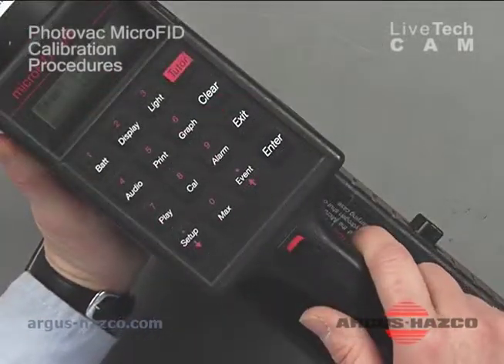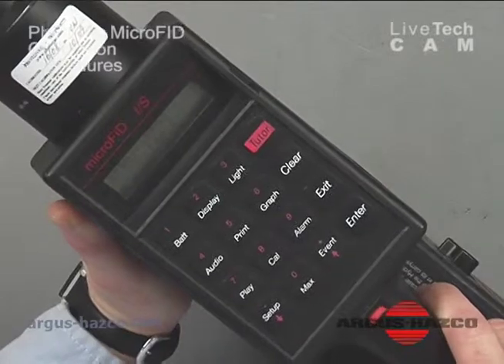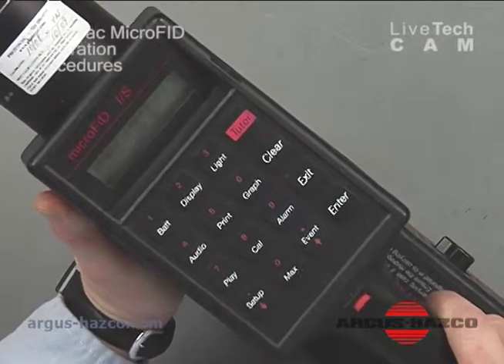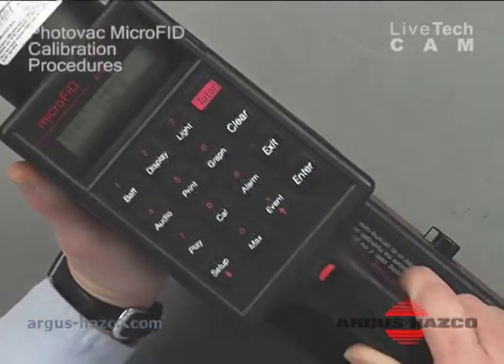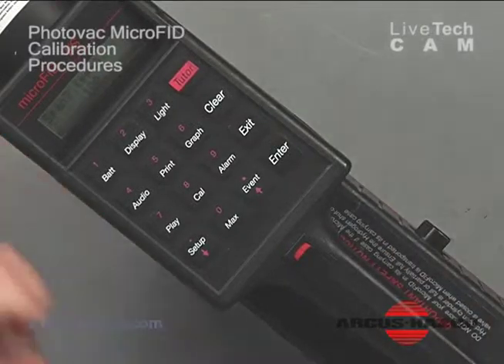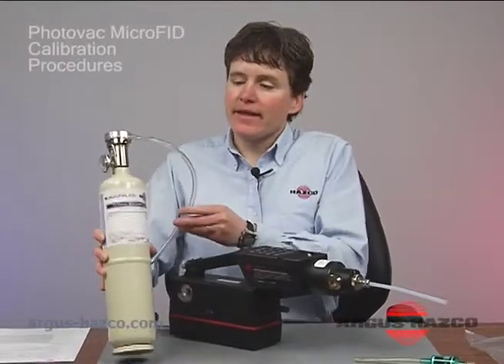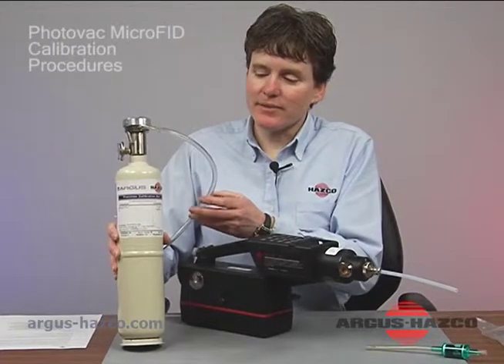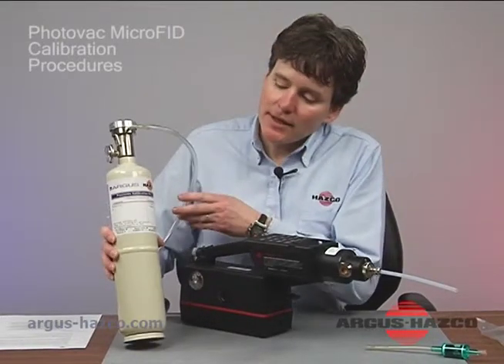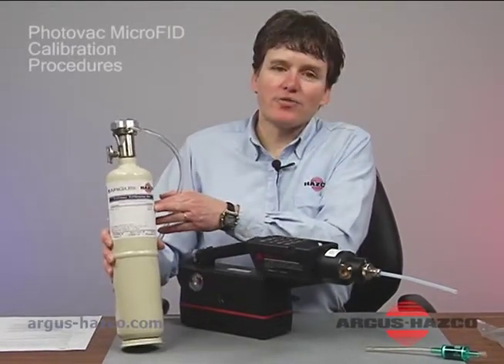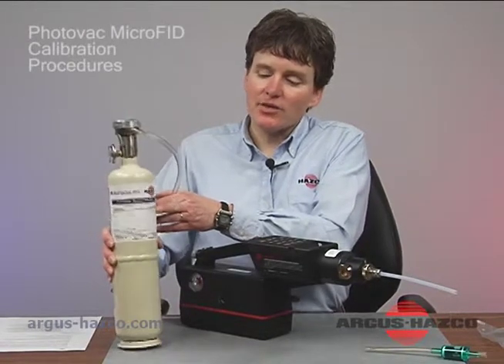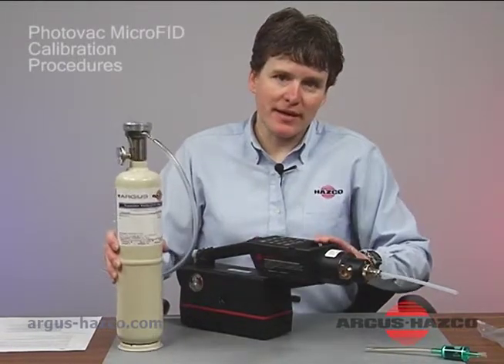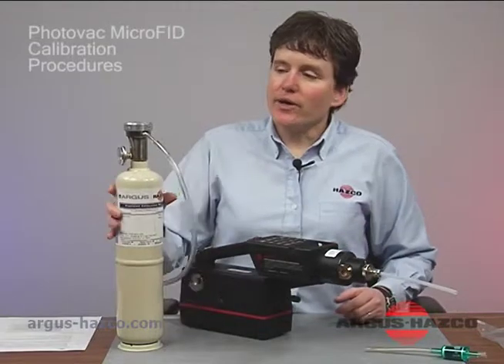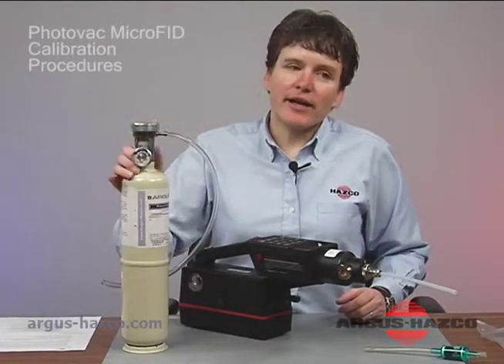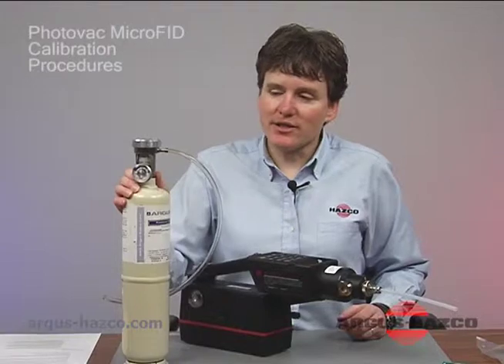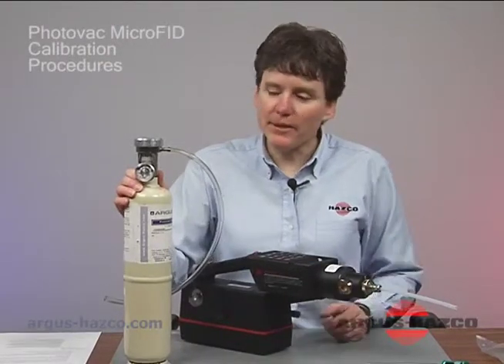Okay, once it sets the zero point, the next screen you'll see is span ppm. I already have 100 ppm typed in, and this matches my calibration gas that I have supplied or purchased with my rental. My calibration gas is balanced 100 ppm methane. So I want to make sure this number matches my monitor. We are using a demand flow regulator, so we don't have to worry about matching the flow of gas with the flow of the pump.